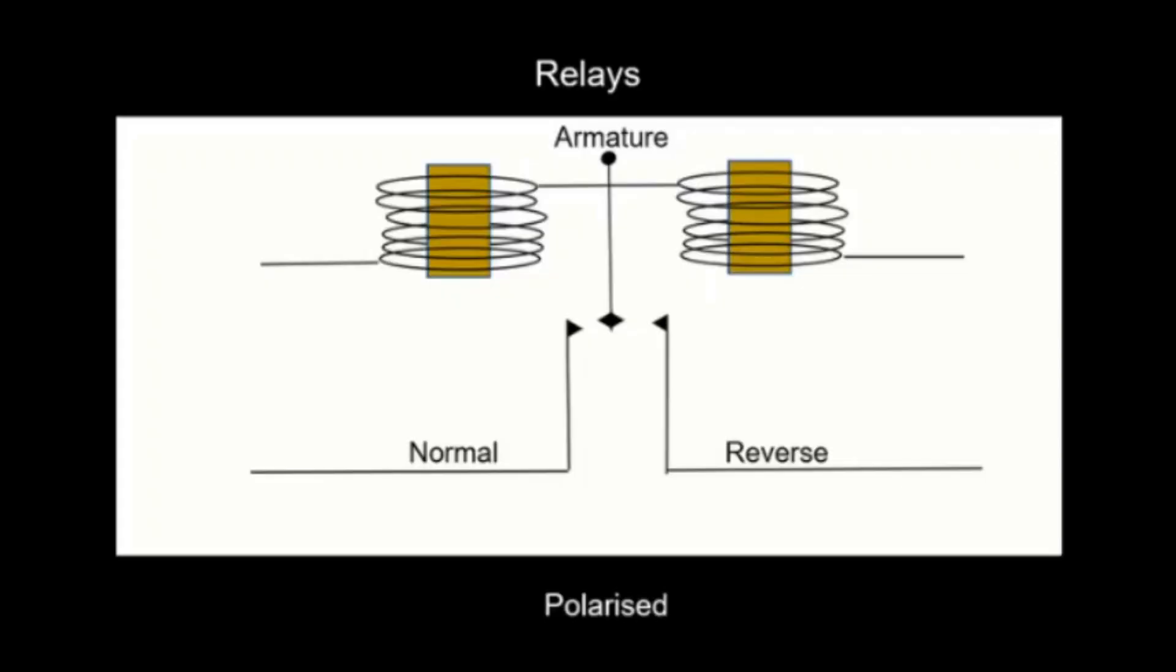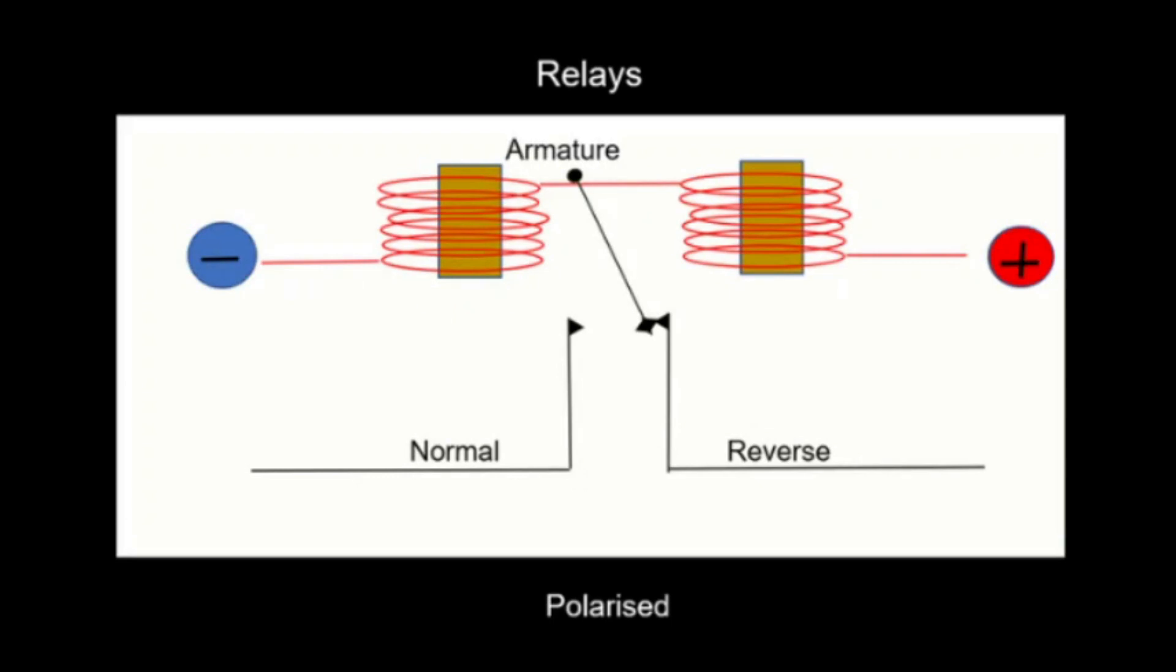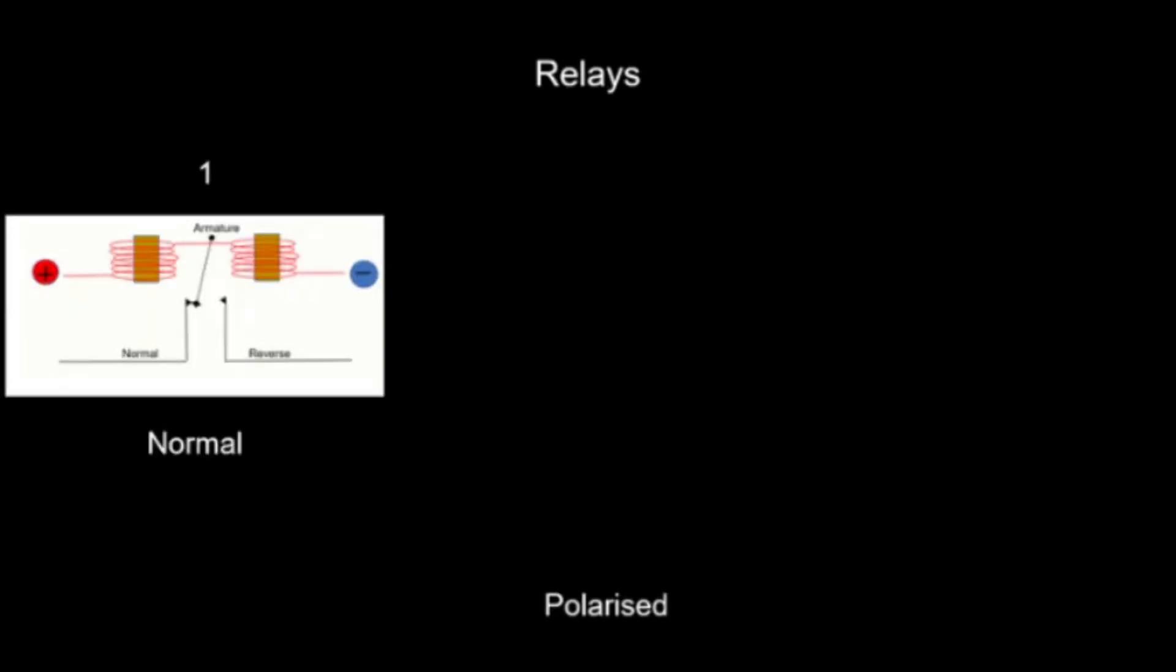One method of achieving the proving of three possibilities is to replace the non-polarised relay with a polarised relay. This relay, as its name suggests, is polarity dependent. If we energise the coil of the relay with the polarity reversed, the armature will move in the opposite direction. A polarised relay is therefore able to detect three positions.